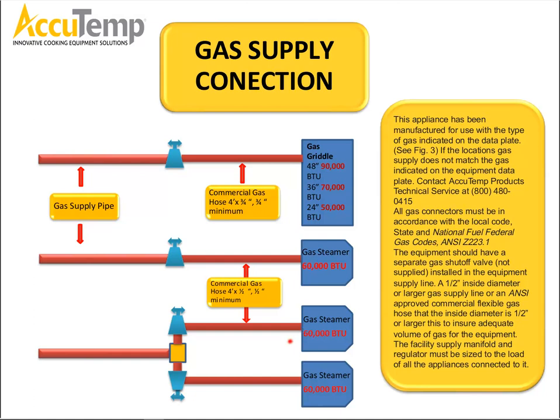And in those situations, what we find is either the top or bottom or both steamers will start going to an ignition lockout. Ignition lockout means it's no longer seeing flame and it shuts itself down for safety reasons. We've seen this a lot, especially in situations where it's intermittent. It's dropping out randomly, and of course, we send a technician out there and it's working fine. So at that point, that's when we start digging deeper into gas connection, gas supply, gas volume, gas pressures.